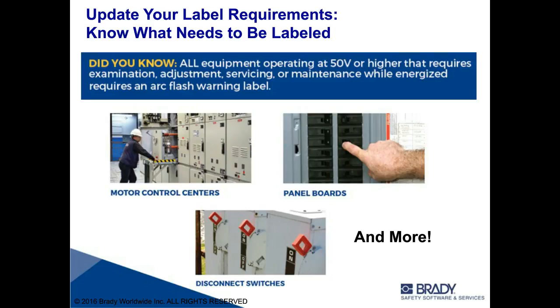Disconnect switches are a very common piece of equipment that's not specifically listed in the code, but that's something that often is opened up, so people are exposed to it while energized. And you do testing or troubleshooting at that disconnect switch, and that is an arc flash risk and should be labeled.